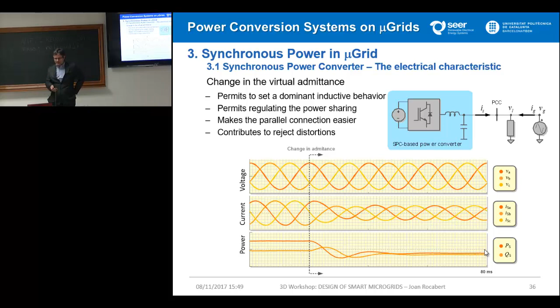As I say, this system can permit setting a dominant inductive behavior also in low voltage lines. This is an advantage - it permits easy regulation of the power sharing between converters, because now the power sharing of the converter is determined by the output virtual admittance, in the same way as a synchronous generator. Also, since this virtual admittance system is imposed by an integration, this contributes to rejecting distortion in the grid.